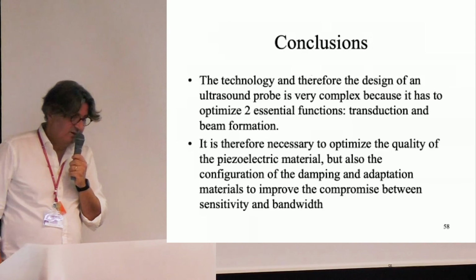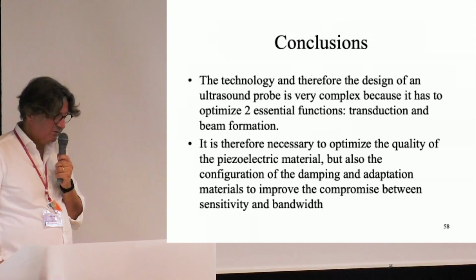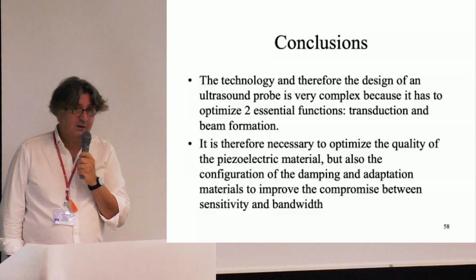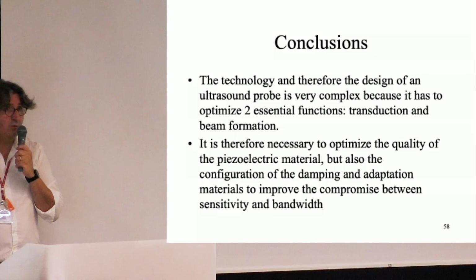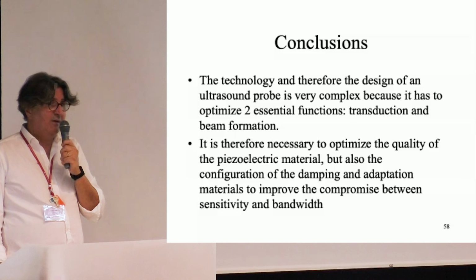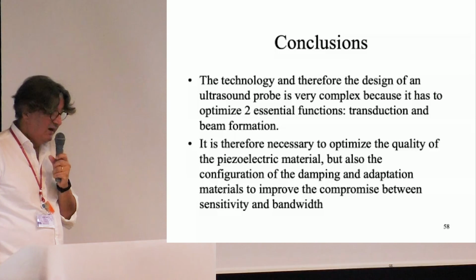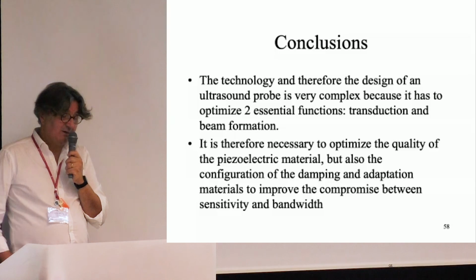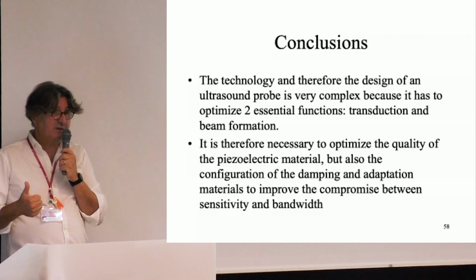So the technology, and therefore the design, of an ultrasonic probe is very complicated, you understand? Two essential functions have to be optimized: the transduction on one side, and the beam forming on the other side. It is therefore necessary to optimize the quality of the piezoelectric material.